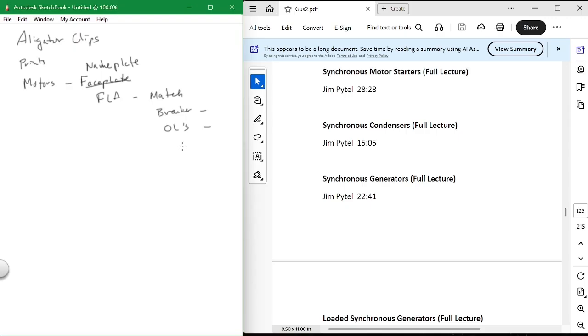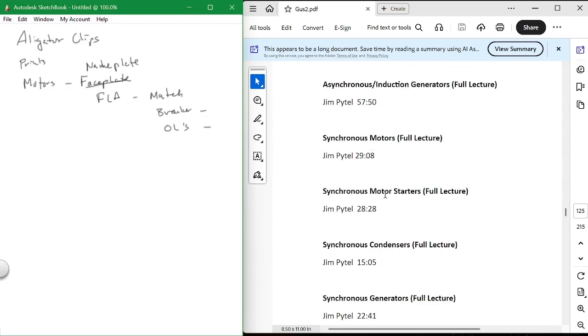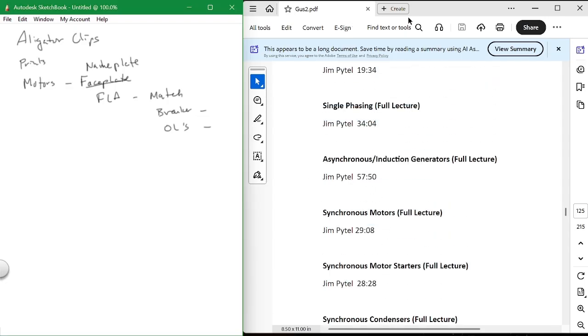So that's what you need. And that's simple, but yet very profound. You have to go a little bit above, but not by much. That's your overload settings, and you have to get those, or it won't run, okay? Now, the motor might not be wired yet. You want to inspect to see if it's wired and all that kind of stuff, but that's where you're at. So I want to go back and I want to look. I'm going to cheat a little bit today.